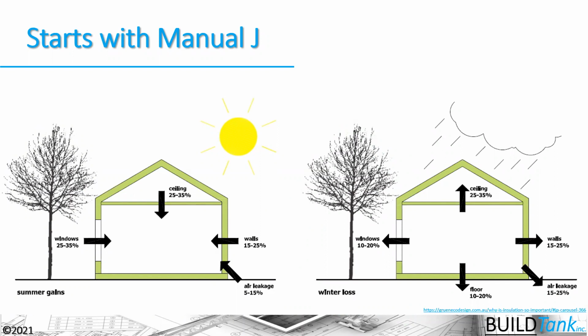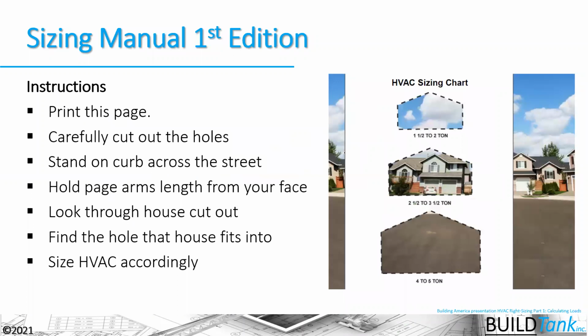And we now use a software to help us develop that manual J and develop that heating and cooling load for that house. Whereas in the past, we used a lot of rules of thumb and estimates and guessing about how to actually size the equipment for that house. We should be limiting any guesstimate in this, and we should be using empirical data now when we're doing an HVAC load on that house.